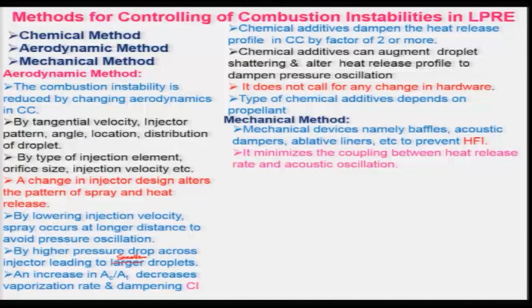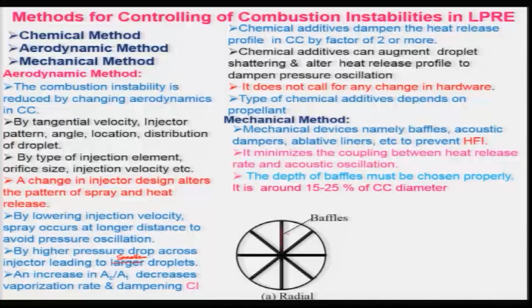And let us look at the baffles. These are the baffles shown in a planar way, but perpendicular to this plane there is a depth, and the depth of these baffles must be chosen properly such that it can separate the combustion, and then combustion will not be interlinked with each of the sectors. These are also sectors, right. Sectorial combustion will be taking place, such that the pressure can be dampened. Generally 15 to 20% of the combustion chamber diameter is used as the depth of the baffle. This is a little design thumb rule which is being used.